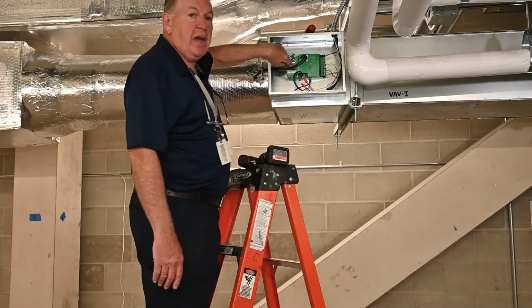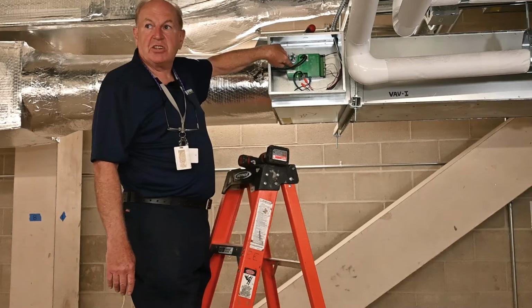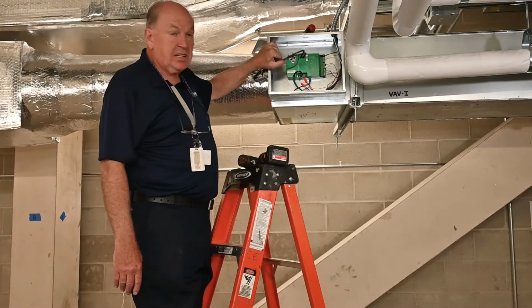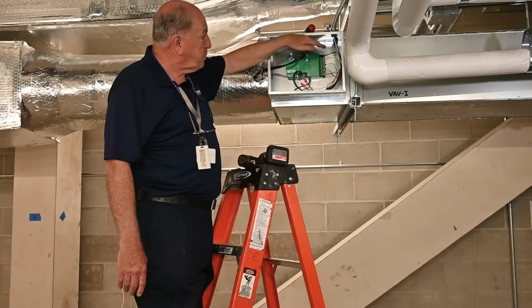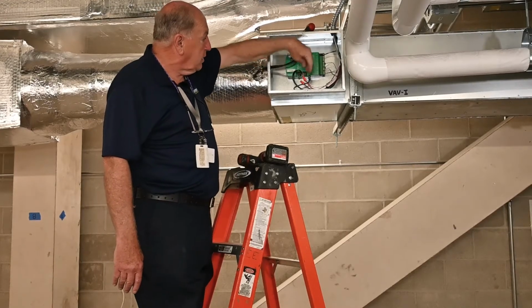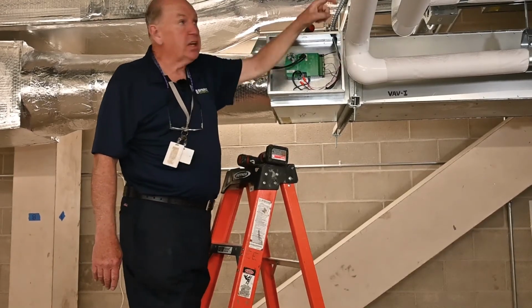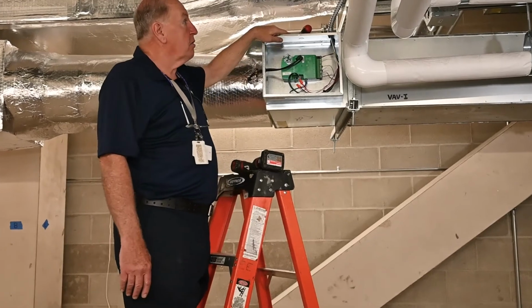So this is a KMC damper actuator. It's actually a VAV controller. It has the sensing lines on it. It has power. It has a comm line. And it also controls the valve, the reheat valve.